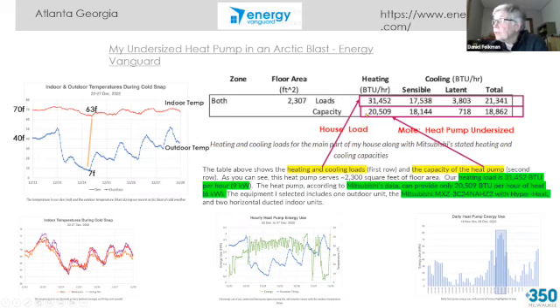It's undersized both for heating as well as cooling. The total cooling demand for the house is 21,000 BTU, and the heat pump itself can deliver 18,000 BTU.